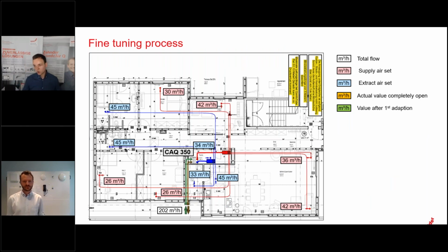Now let's take a look at the process of fine-tuning. Here you can see a typical layout for a family house. We have a central unit, the ComfoAir Q350, outdoor air connection with ComfoPipe Compact 160, and indoor connections with ComfoTube 90. And for the outlets, we used Luna valves. The total volume flow, so nominal ventilation, is 202 cubic meters per hour, according to the calculation based on DIN 1946. In red, you can see the supply air set points, so the calculated values, and in blue the extract air set points. For convenience, we only take a look at the extract air flows, so the blue ones.